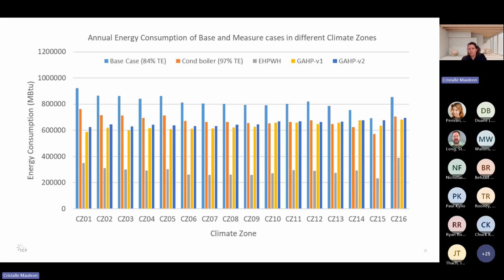So as we would expect, the base case consistently shows the highest energy use across all the climate zones. The electric heat pump case shows the lowest site energy consumption thanks to its high coefficient of performance, which was 3.2 in our model. The GHP version 1 performs better than version 2 because it's preheating the makeup and the recirculation water, leading to greater energy savings. The condensing boiler shows modest improvements over the base case, but it's not as significant as the heat pump-based systems.